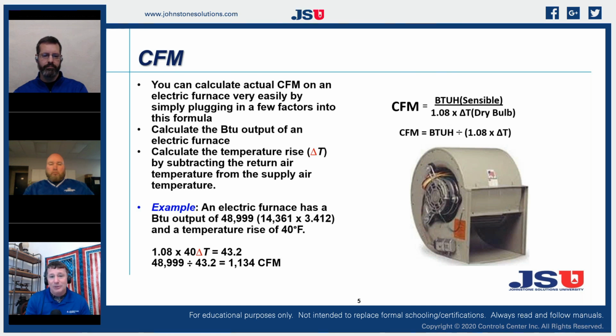Well, now all I got to do is check my temperature rise. Check the temperature from my return to my supply. That difference, that delta T, is my temperature rise, just like I was checking temperature rise on a gas furnace. If I simply use that 1.08, which we're going to say is a constant, but it is not, I'm going to explain that one here in a minute. We're going to use that as a standard number.